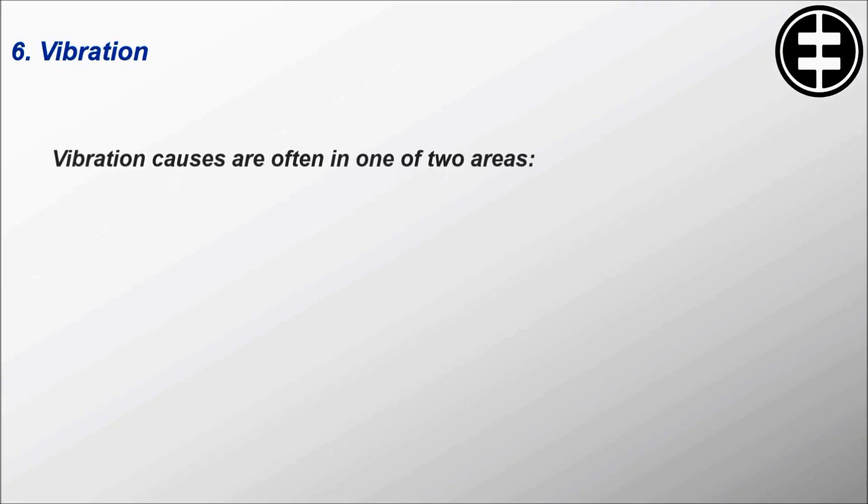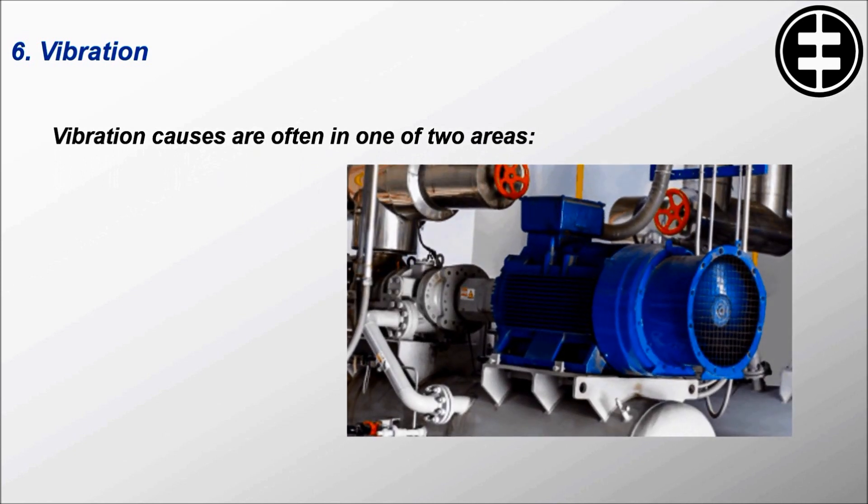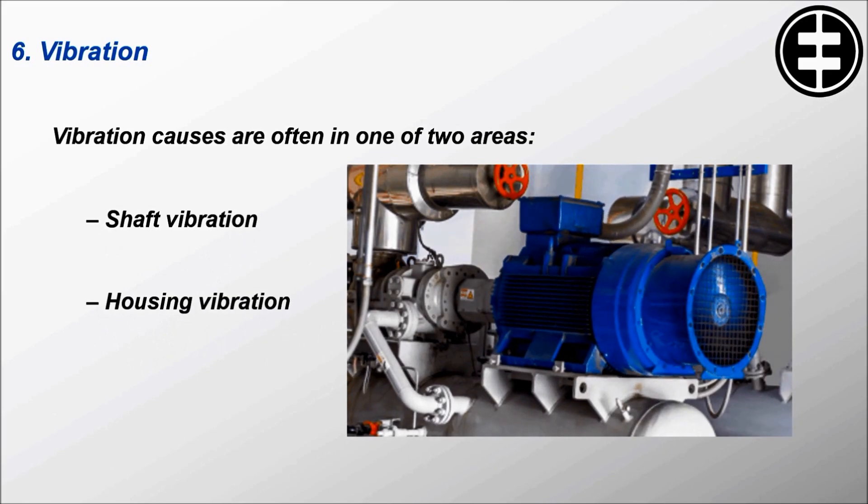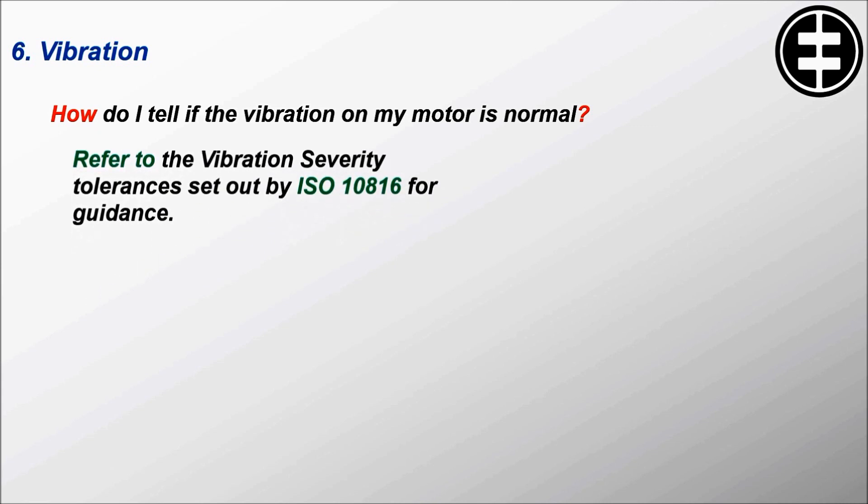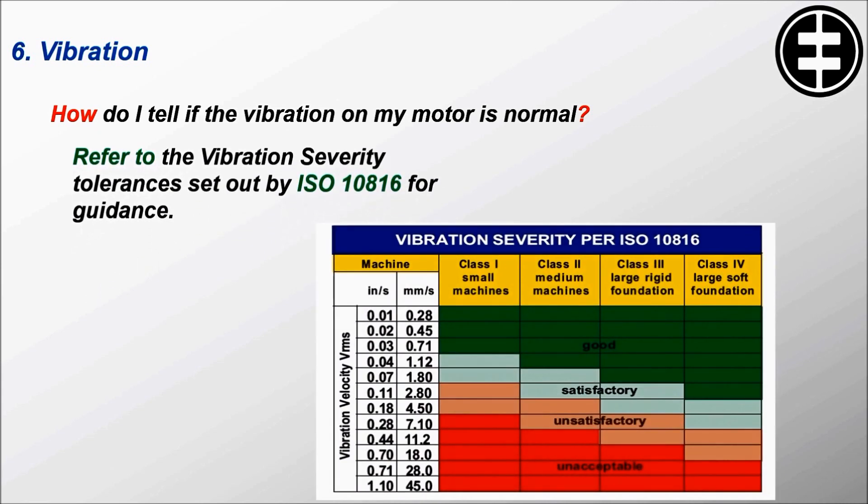Vibration causes are often in one of two areas: shaft vibration or housing vibration. How do I tell if the vibration on my motor is normal? Refer to the vibration severity tolerances set out by ISO 10816 for guidance.